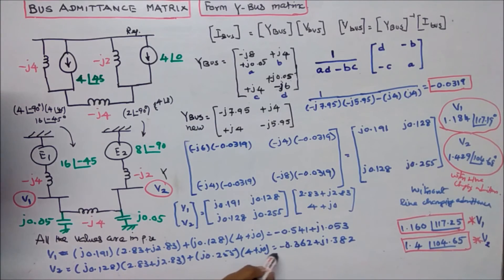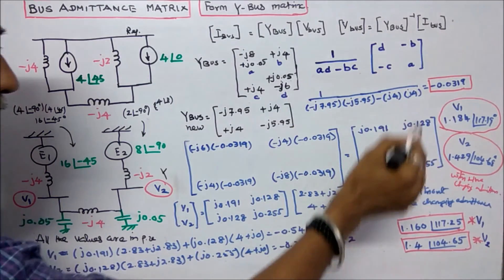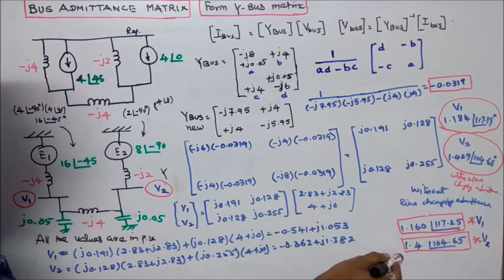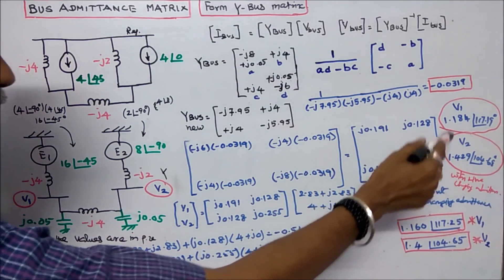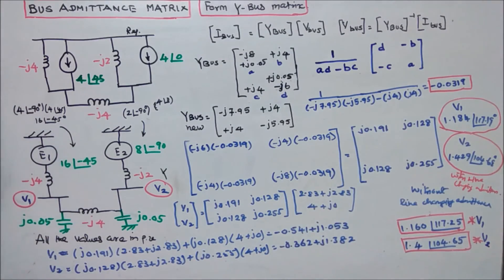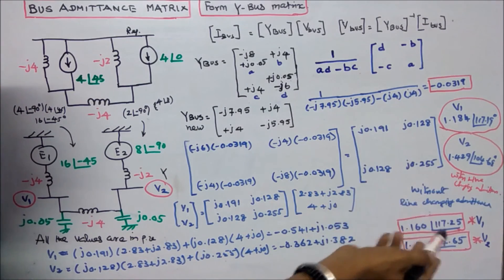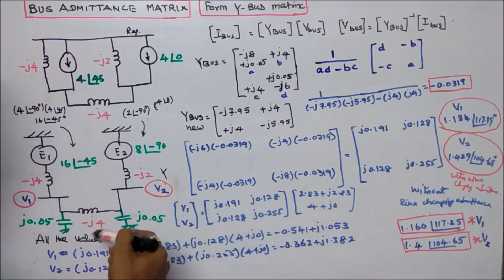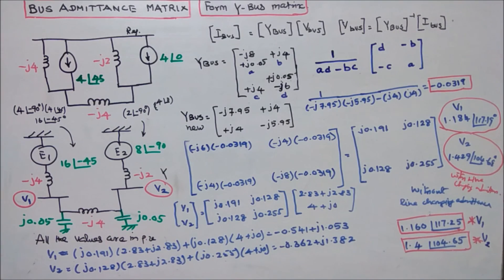Similarly, V2 in rectangular form equals minus 0.362 plus J1.382. In polar form, V2 equals 1.429 angle 104.68 degrees. Without line charging admittance, V2 was 1.4; with line charging admittance, V2 is 1.429. With line charging admittance, there is a slight increase in voltage for both buses. With this, I conclude my lecture. Thanks for listening.